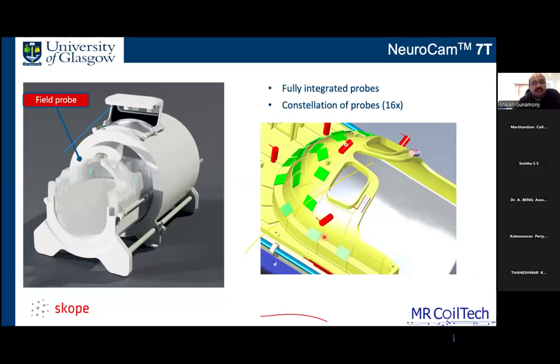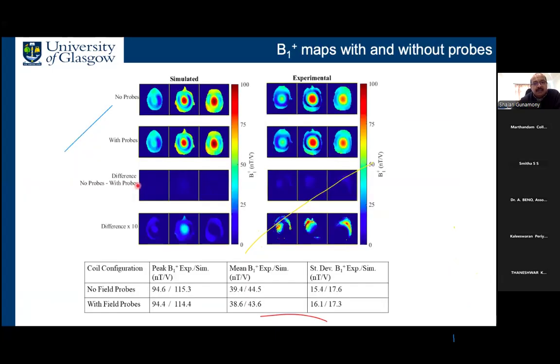But we integrated 16 of them inside the coil housing. And finally, from externally, it just looks like the normal coil. But you can see here the probes are fully integrated inside. And when we put in so much more electronics inside the coil, we also have to make sure that we are not creating any safety issue. The probes are not heating up. The probes are not altering the spatial distribution of the B1 field and so on.